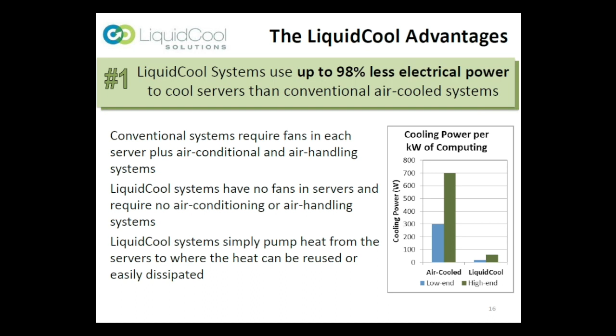The first one and the most obvious one is that we use a lot less electrical power for cooling. And the reason for that is that conventional air-cooled systems need to use fans, both to circulate air through the servers and then to deal with the heated air that's removed from the servers. So typically, for every kilowatt of power that's used for the servers to do useful work, between 300 watts and 700 watts of additional power are needed to cool air-cooled servers. By comparison, for every kilowatt of useful work that a liquid immersion cooled server would need, only about 20 to 60 watts of additional power are needed for cooling. And the reason for that is that we don't have fans in our system, and the pumps are far more efficient than the fans and use a lot less power.